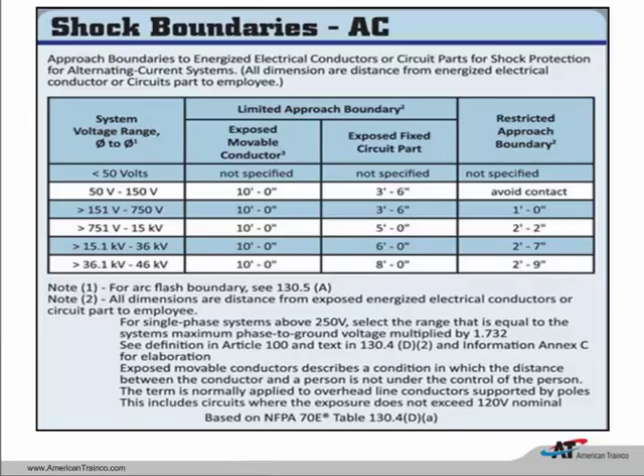The belief, especially from IEEE data that we found, is that 120 volts is not enough voltage to sustain an arc through the air. It's not going to ionize the air. It's not going to turn the air into a plasma. We're not going to see a fireball. We're not going to see the copper get heated up to 1,981 degrees, and we're not going to see it vaporize. So the tables are helping us a little bit.